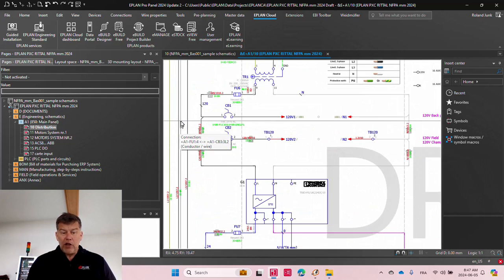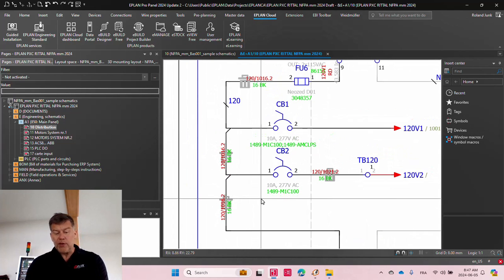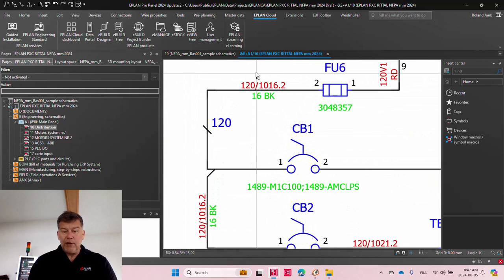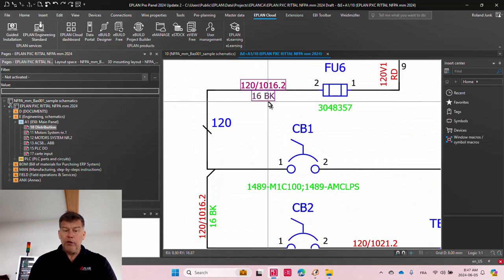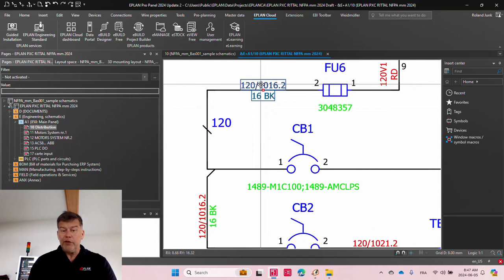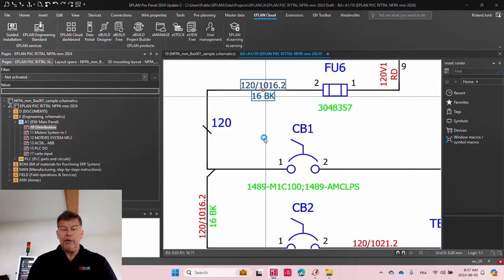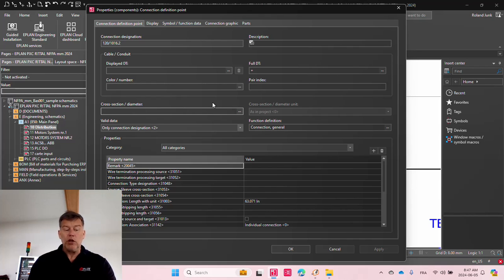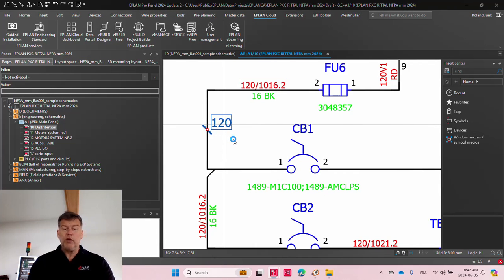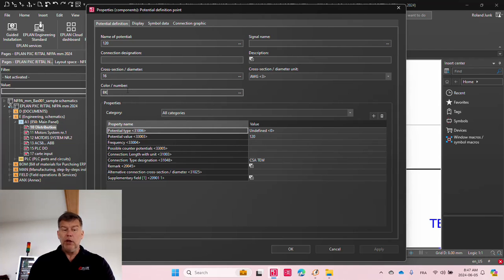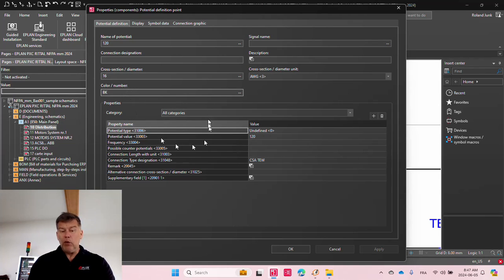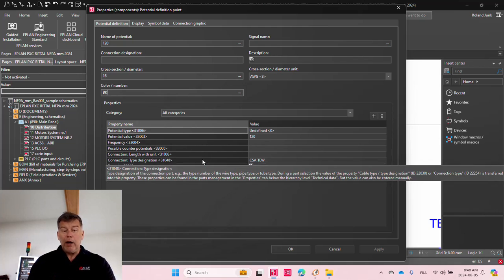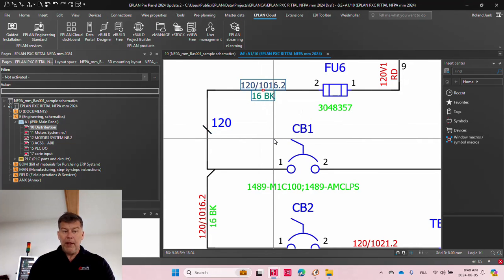If I actually get closer here, you will see how this works. Basically, as you can see here, the wire number is above the wire and just below, we actually have the 16 BK, even though it's not even assigned on the connection definition. Why? The reason is simple: because we go to the potential value here and we assign a cross-section BK, we assign it here. And this then gives me automatically this display here.